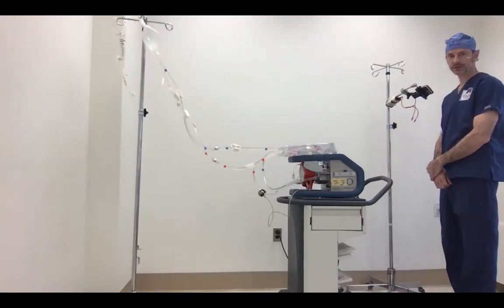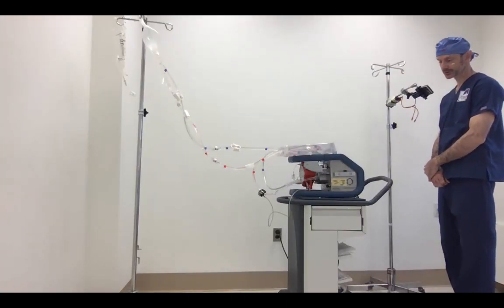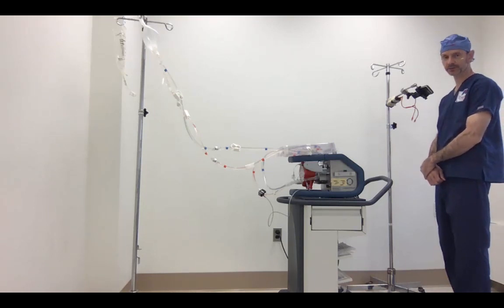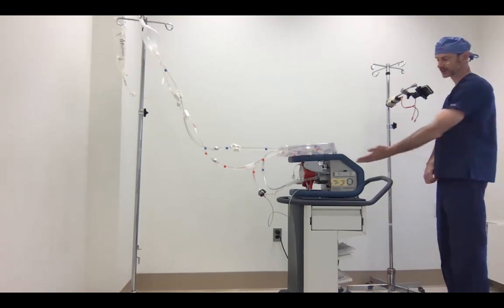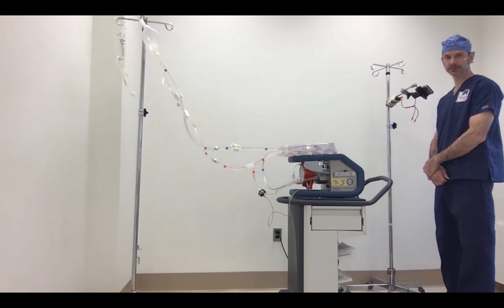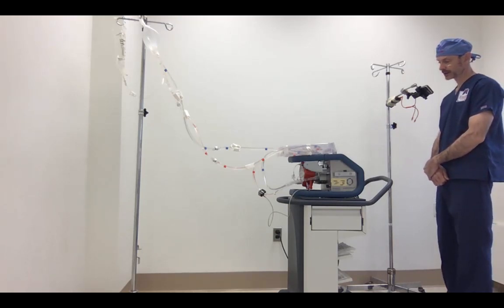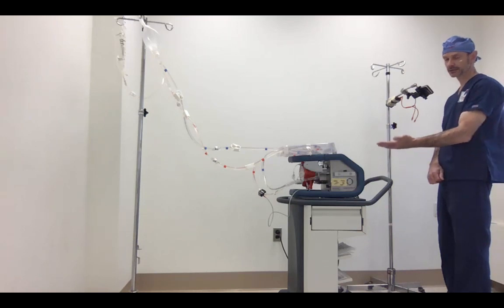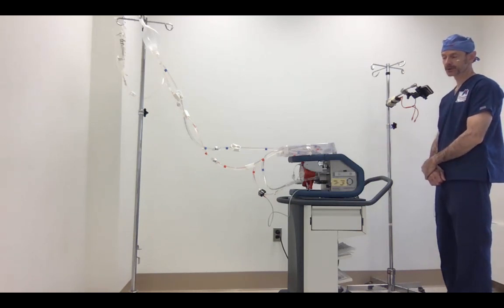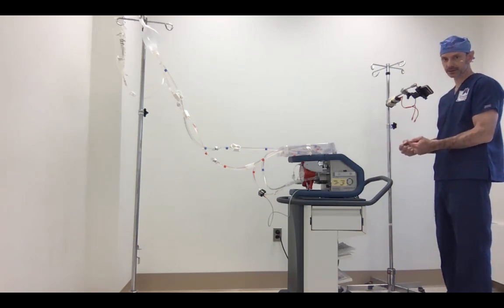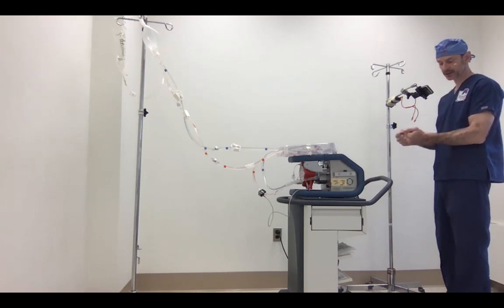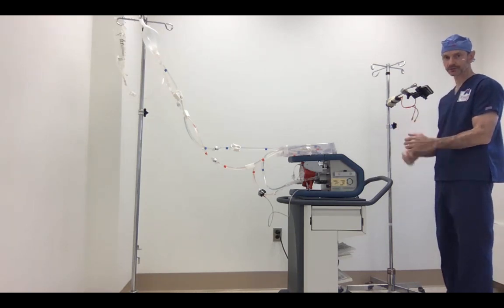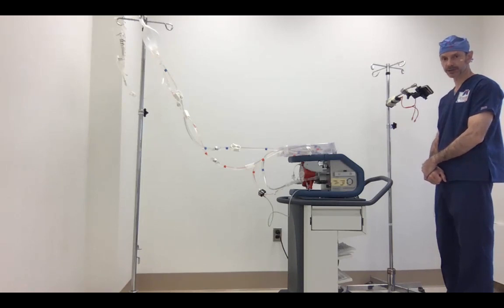Now, I've given this demonstration dozens and dozens of times, and I've often been asked, do we have to wait this long? And certainly at 7 minutes, no, we wouldn't. The manufacturer would suggest you only have to wait about 4 minutes. It takes about 4 minutes to prime this thing, and it does it very effortlessly all by itself. But just to prove the point, I have stopped the priming as soon as we didn't hear air anymore, and then disconnected the cassette, the oxygenator and pump system, and taken it out and shaken it around and looked for air, and there was no visible air that I could see with my eyes.